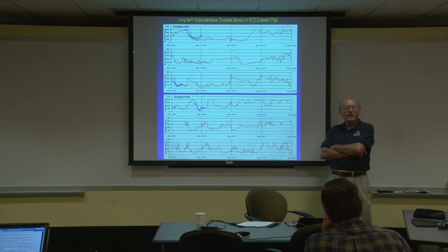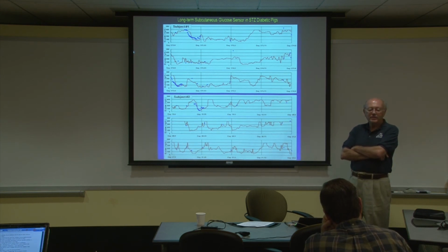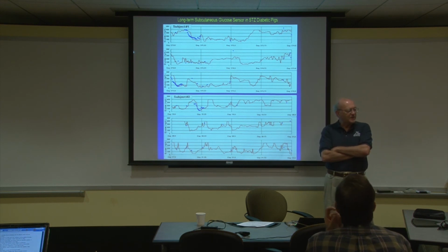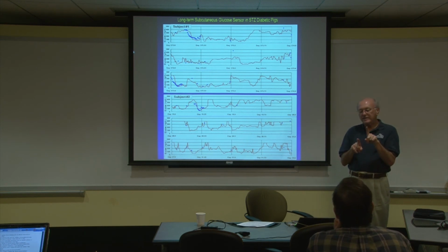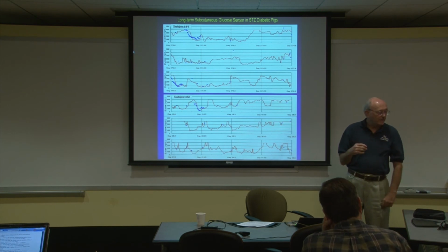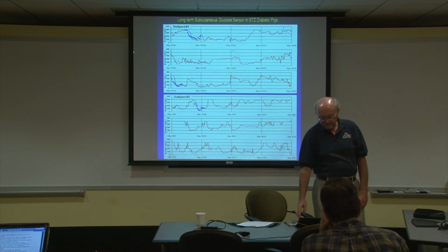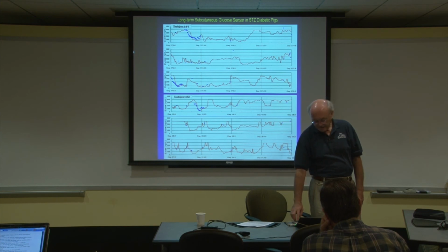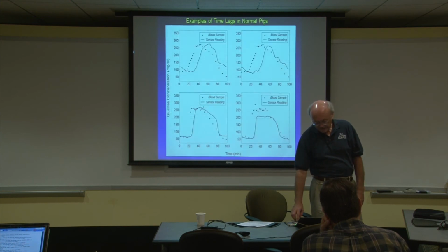The other message is that an implant in the tissues can be there for a long period of time and be totally functional and effective. Most people say, well, how's that possible? Well, this gadget has the reference oxygen sensor and the oxygen-based glucose sensor on the same implant. Of course, there's a capsule that forms around this, no doubt. But that capsule affects both sensors simultaneously, so it does reduce the oxygen transport to both of them. You take the difference and you can largely eliminate the effect of the capsule. So it's kind of a design strategy, and this is proof that it works.